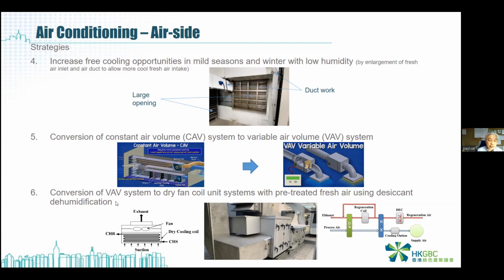Another one is that they use the fan coil unit system together with the PAU systems. The fan coil units are only used to do sensible cooling. They do not need to do dehumidification, because dehumidification by fan coil units is not well performed. By using this approach, the latent load is catered for by the fresh air unit or the primary air unit. The primary air unit has a desiccant dehumidification system installed together with the cooling, so it treats the fresh air to ensure the humidity of the space is good enough.